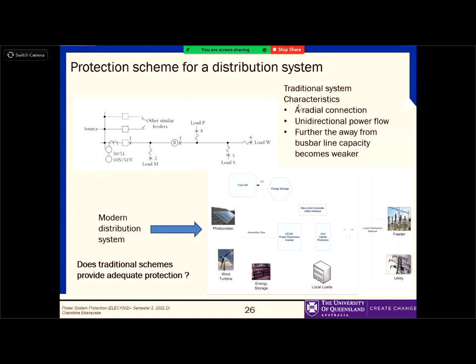So in traditional systems you are looking at only one direction. In a modern system, sometimes you may have to look at both directions, and you have to understand that reverse power flow is allowed, whereas in traditional systems reverse power flow is not allowed. So you may have to make a lot of setting modifications in a relay. You don't have to replace the whole hardware, but you may have to change the settings. As I said, we will discuss this in more detail in the latter part of the course, about distributed generation and what sort of protection schemes are associated with it.